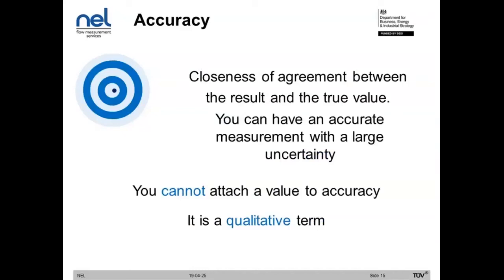The difficulty with accuracy is that it's a very useful term to use, but it's a qualitative term. You're not supposed to attach numerical values to accuracy, so it's not technically correct to say this device is 5% accurate. What you can say is that the device performs to a 5% uncertainty, for example. It's fine to say that this device is more accurate or less accurate than a different device, but the important thing here is not to attach a numerical value to a qualitative term.